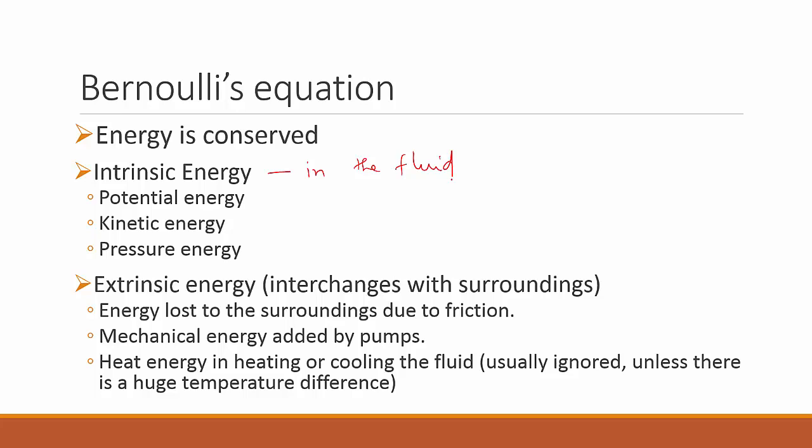The extrinsic energy is the frictional loss, and the mechanical energy added by the pump, which is our interest, right? Sizing a pump or a fan. The heat energy in heating or cooling the fluid, the thermal energy, can be considered, but we are going to ignore it in this text. For most applications it holds true. Unless there is a huge temperature difference, the thermal energy is relatively negligible.